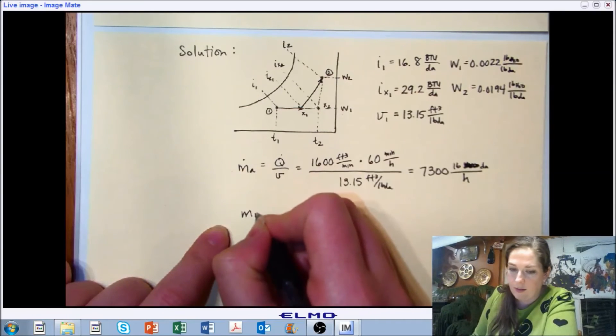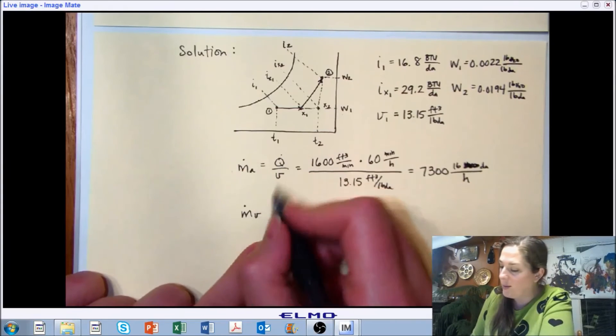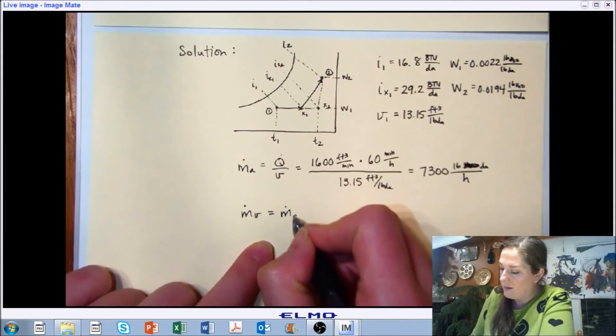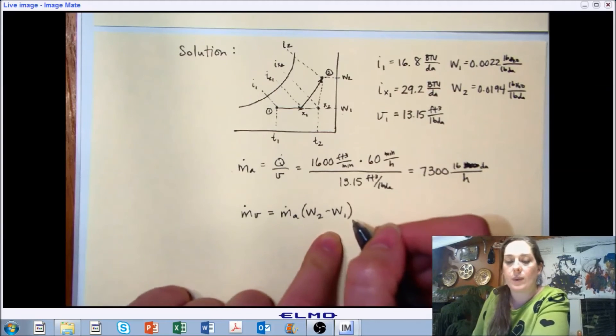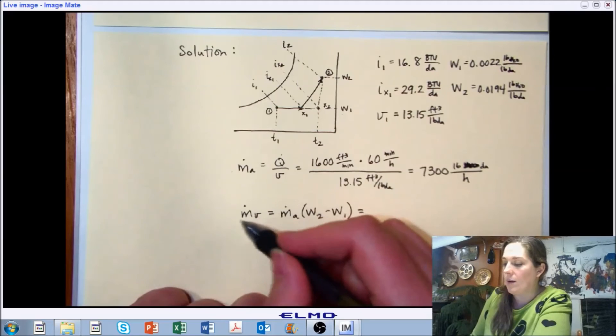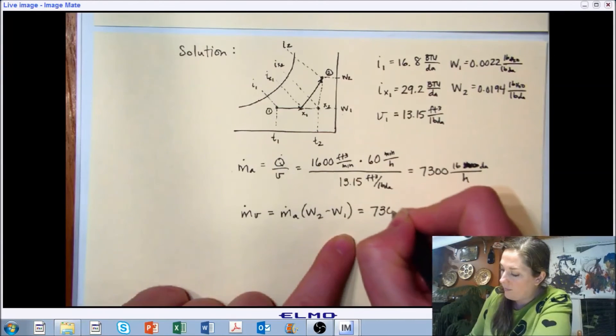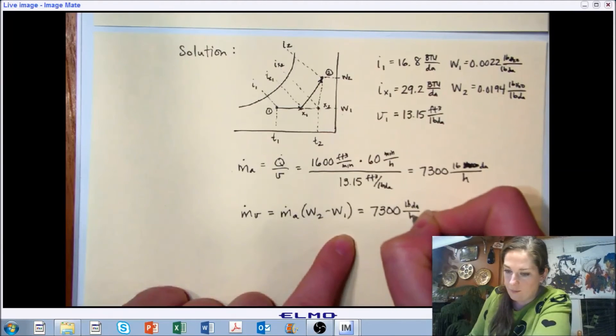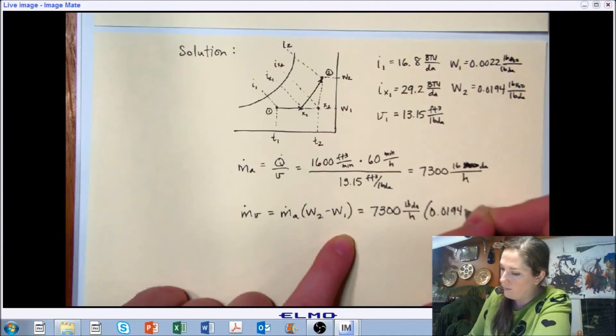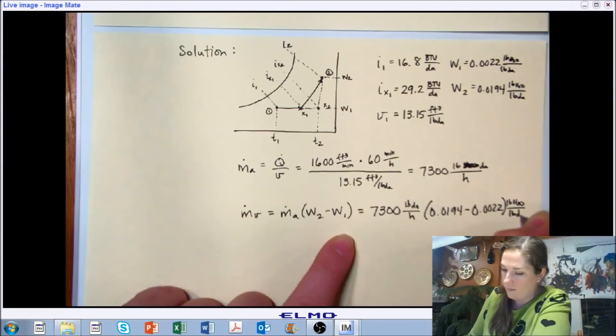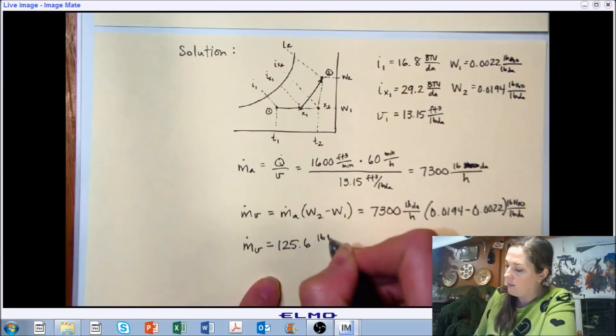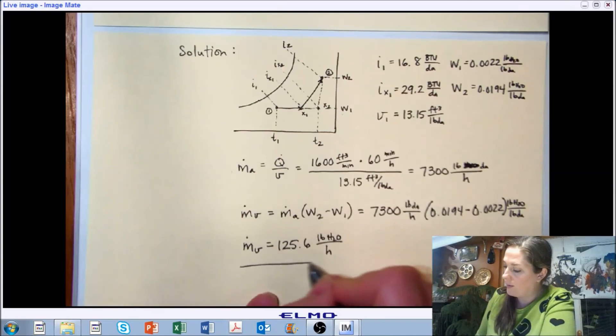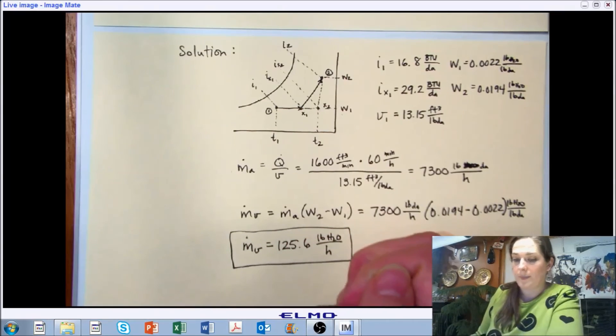And then if we want to look at the amount of water, this is where I've got to head on my units. And it's related by the amount of air we're moving and the change in moisture content of that air. So this is the amount of vapor that we're going to need to supply. And so the amount of vapor that we need works out to be 125.6 pounds of water per hour. That's a lot of moisture.